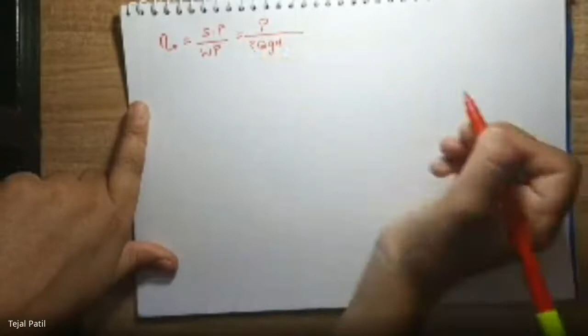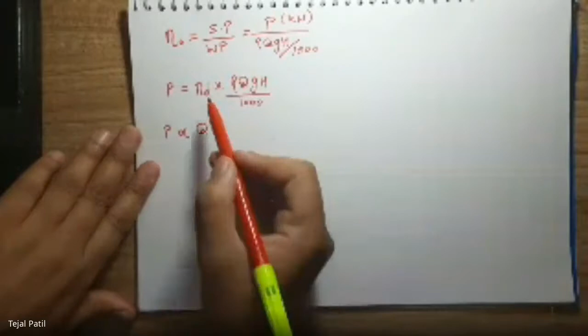Now from this, we can rearrange it: power is equal to overall efficiency multiplied by rho Q g H divided by 1000. Also, we can write that this power is directly proportional to what? We want the overall efficiency to be the same, so it is constant. Rho is constant, of course. Q is not constant, because discharge is going to change. g is again constant, and head is going to change. 1000 is again a constant. We are keeping the overall efficiency the same because we are comparing. So we can write that power is directly proportional to Q and H.